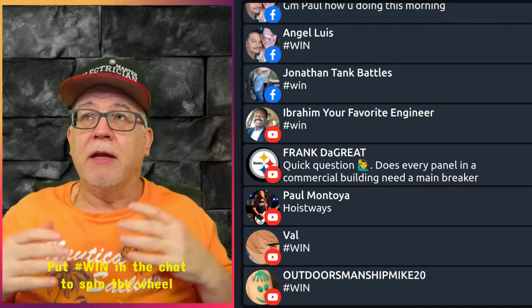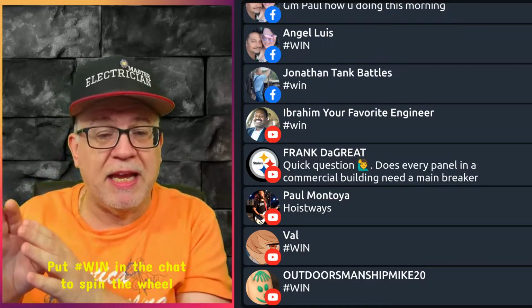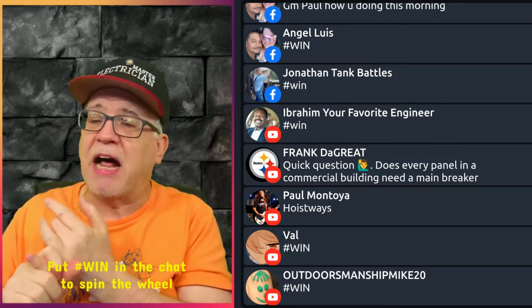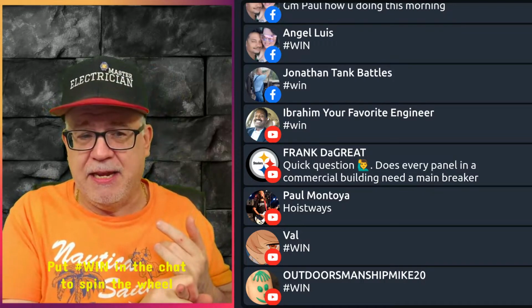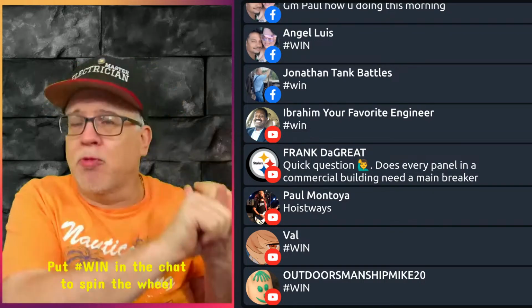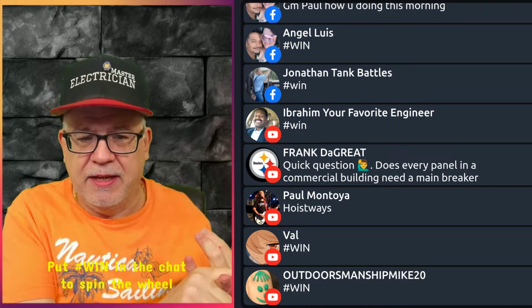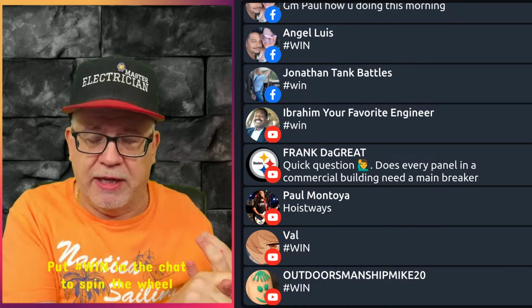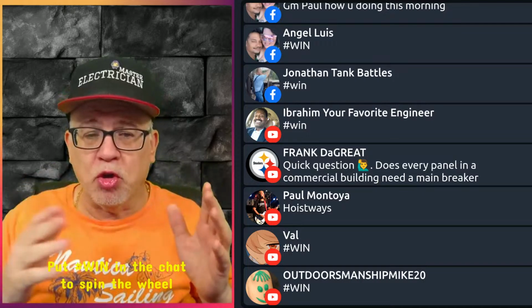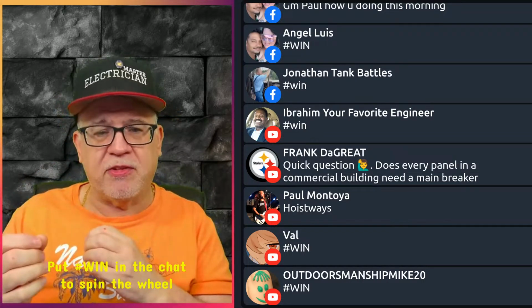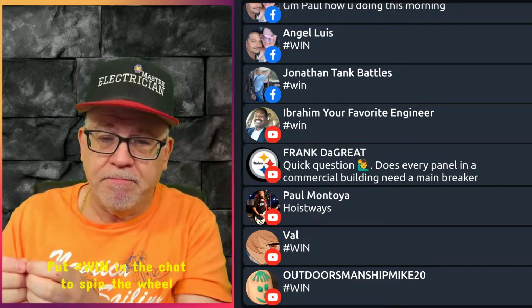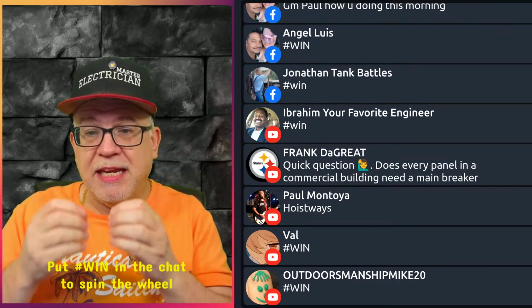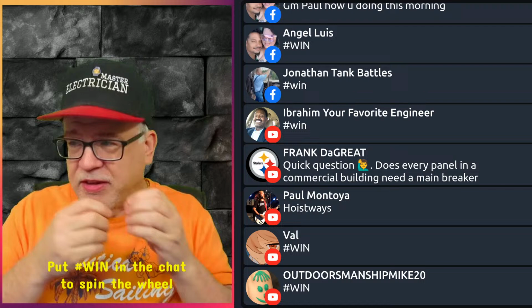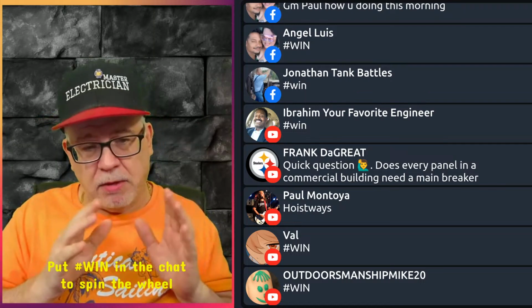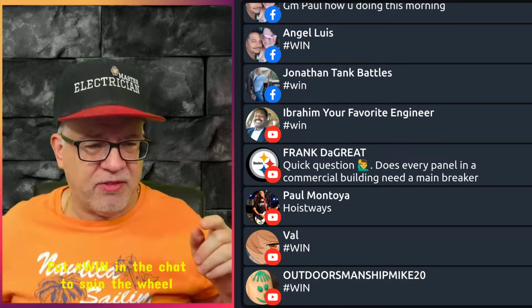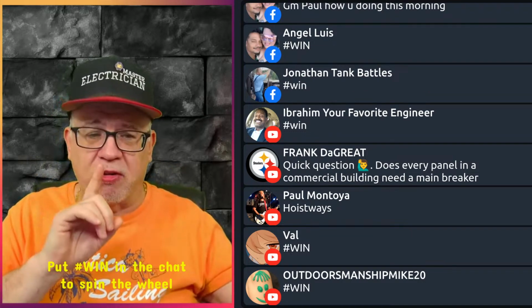Okay, so is it plausible that we could do something? Yes, but you've got to still follow all of the rules for the GEC, and then you still have to follow all the rules for the EGC. Again, a lot of acronyms: equipment grounding conductor and grounding electrode conductor. If you follow all the rules for both and you take all those into consideration, it is possible that you could use the EGC to extend the GEC, okay? Now, what subtle difference is this, though, when it comes to those remote distribution panels? This is a subtle difference.